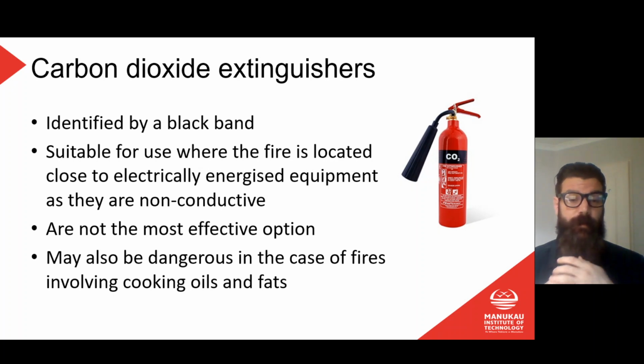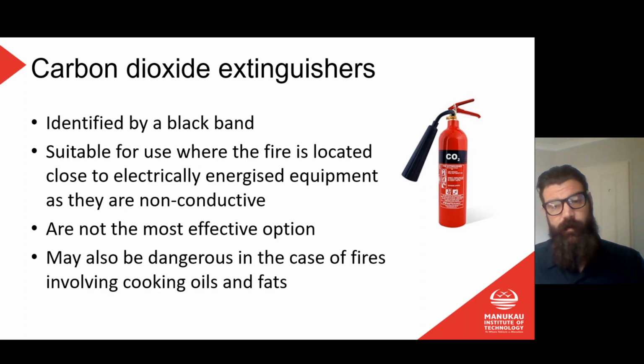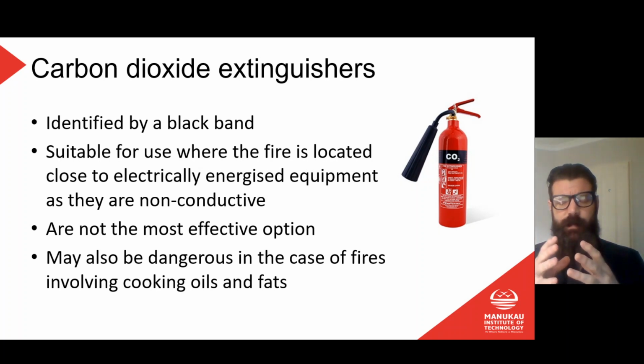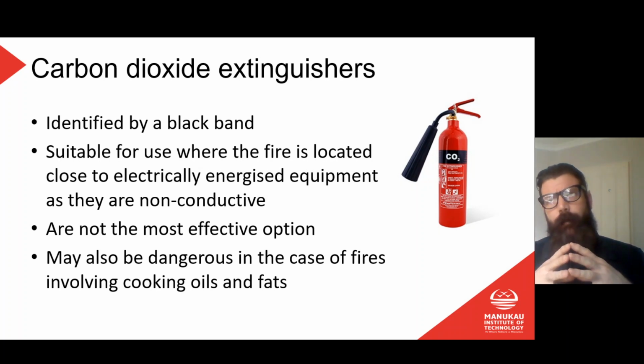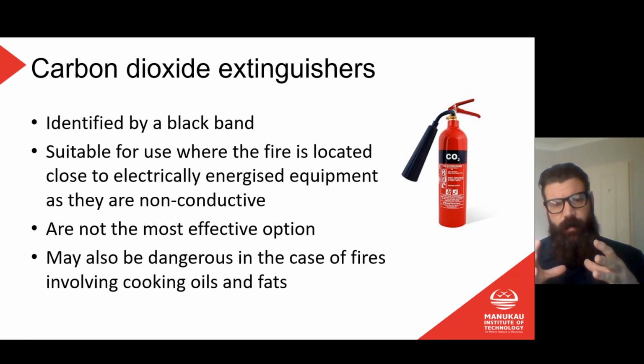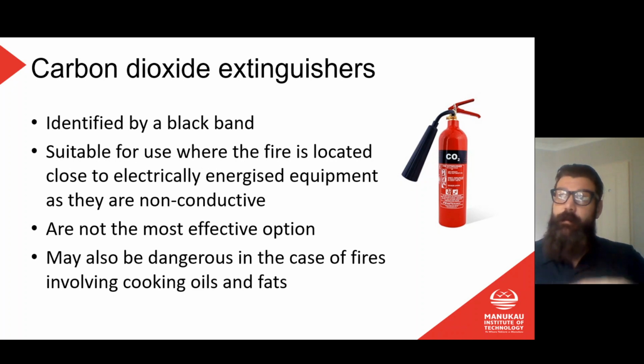They're not the most effective option, and they may also be dangerous in the case of fires involving cooking oils or fats. So let's think about CO2 then and how that prevents a fire. So we're also here talking about starving the fire of oxygen. If no oxygen can get to the fire, then that reaction will cease. CO2 is effective at displacing oxygen. Obviously we can't breathe CO2, it's going to push the oxygen away. So what are the issues there? What are the upsides, downsides?